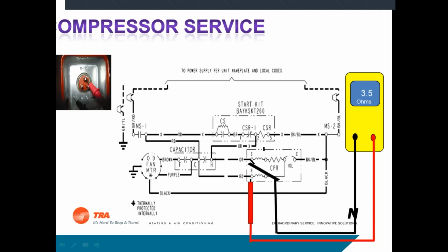But if I go from start to run and I read 3.5, then I know it's my thermal limit that's open. Okay. Now, if the thermal limit's open and the compressor's hot to the touch, give it some time, cool it down, see if it closes. It might have been just running warm. If the compressor's cold and this thermal limit is open, then you got a bad thermal limit. The compressor needs to be replaced at that point.